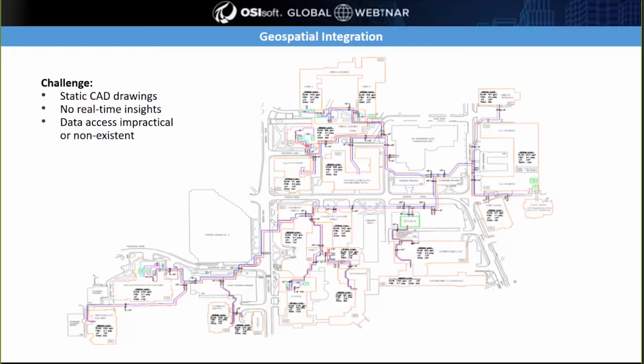Building on that, the next example connects a different utility, chilled water, with a geospatial platform for campus-wide monitoring. This is a standard engineering design drawing for distribution of chilled water across a campus, here at the University of Maryland's College Park campus. Each building has design information for pressure drop, flow, and delta T, but design data rarely represents actual operation. This was another challenge we faced: how do we operationalize these CAD drawings to make them digital and provide real-time chilled water system information?